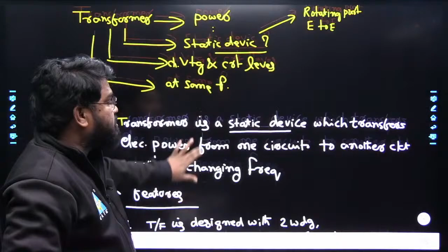So the first feature of the transformer is that it is designed with two windings, one LV winding and one HV winding. But during operation, these two are treated as the primary winding and secondary winding of the transformer. The winding connected to the supply is the primary winding, and the winding connected to the load is the secondary winding.